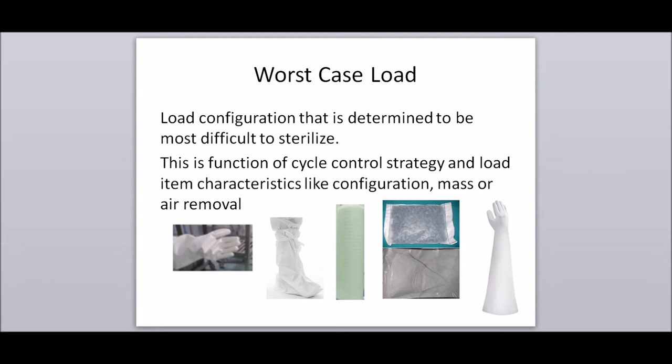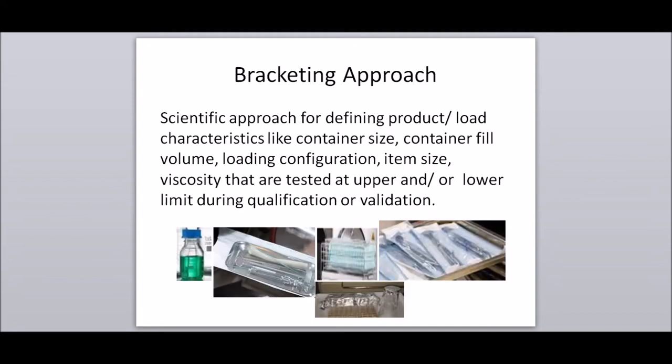For porous or hard goods loads, the worst case may not necessarily be the minimum or maximum load. Bracketing approach: a scientific approach for defining product or load characteristics — such as container size, container fill volume, loading configuration, item size, and viscosity — that are tested at upper and/or lower limits during qualification or validation.